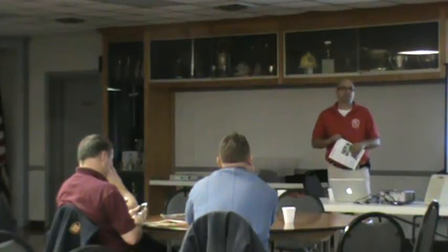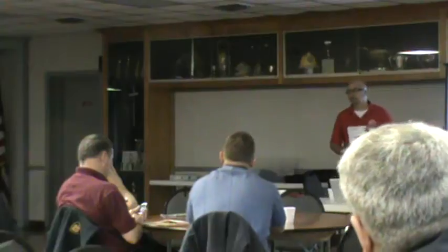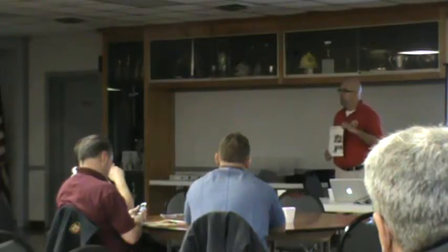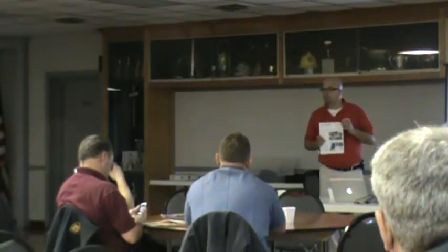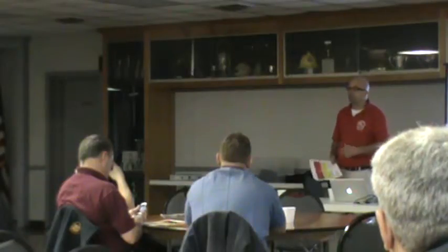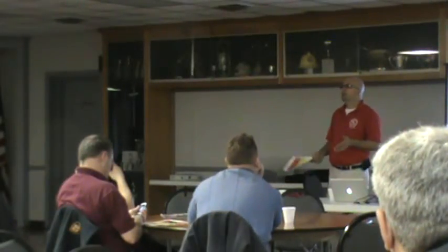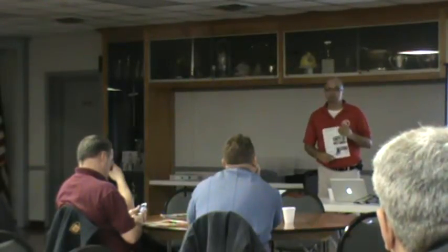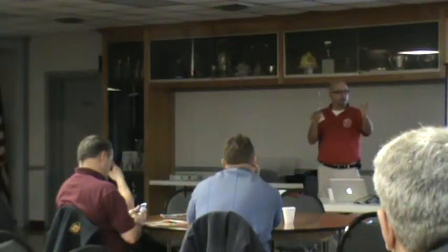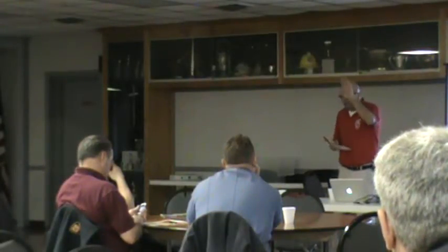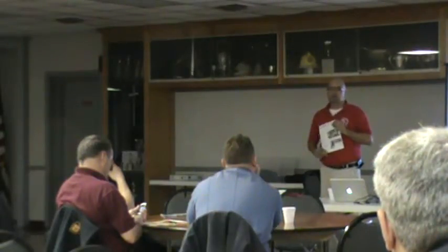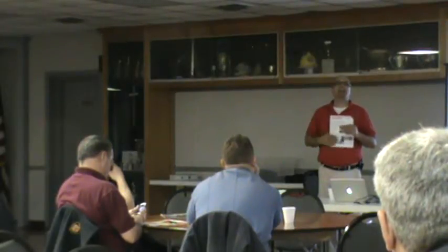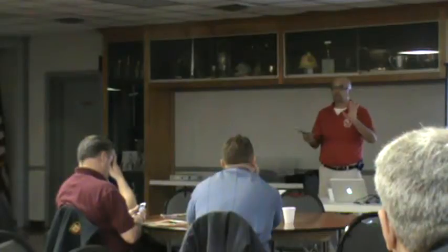Let me tell you the immediate answers. I've got a situation on a fire escape with occupants inside, babies, children, handicapped people, you name it, they're all in there, and you can't close down that building. So, you guys have scaffolding companies down here? If I've got a fire escape on the side of a building and it's horrendous, in a state of collapse, can I order some scaffolding on a typical 5-story building and pay anywhere from $1,000 to $2,000? Not you, the owner. Pay $1,000 to $2,000 and have a scaffolding put right next to the fire escape with full sets of stairs inside, tying back into the building. Will that satisfy the egress for a temporary period of time? Just a scaffold, fully qualified scaffolding that basically gets people out of the building.